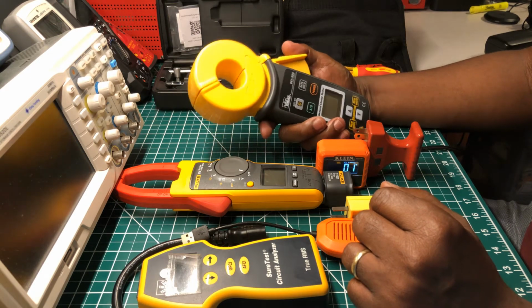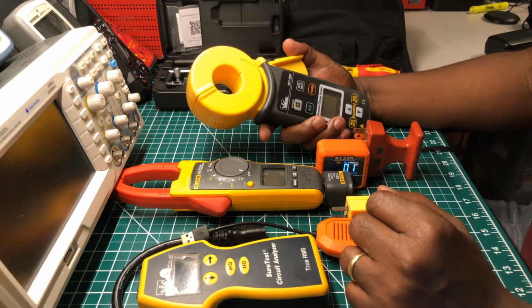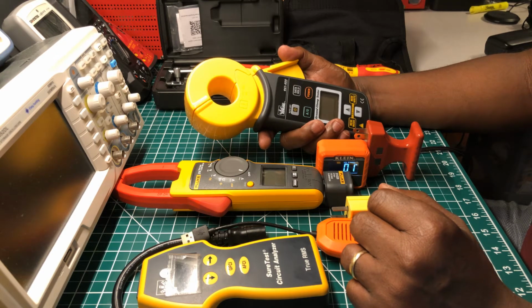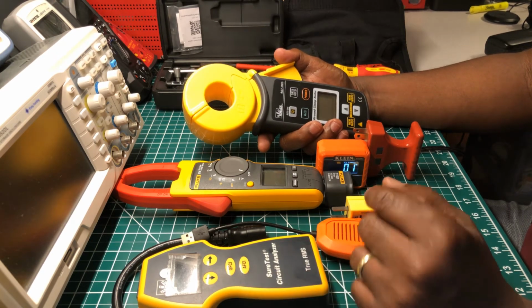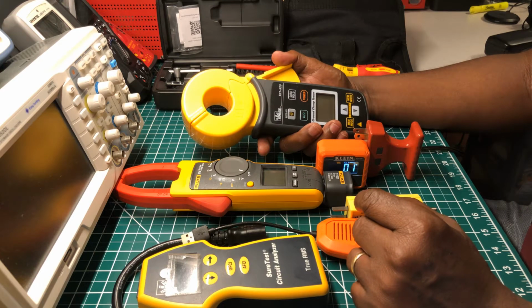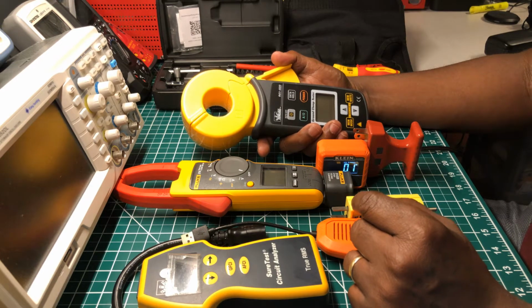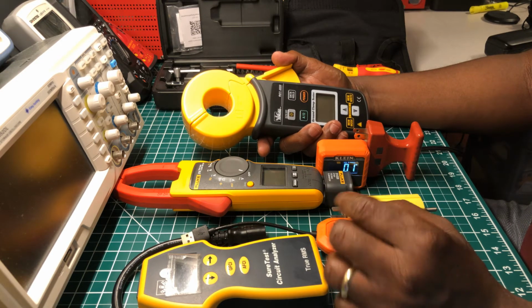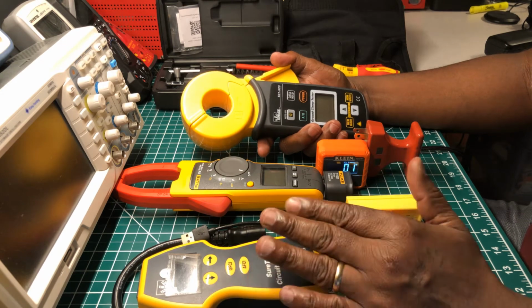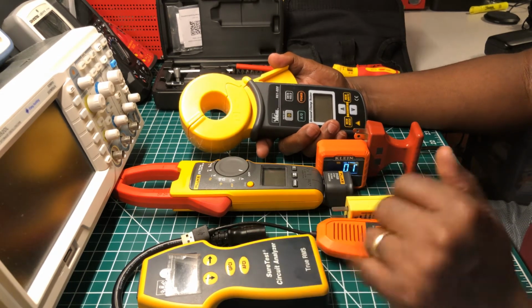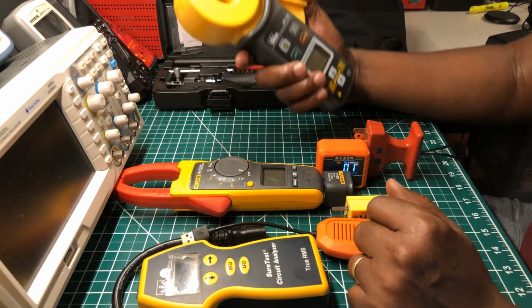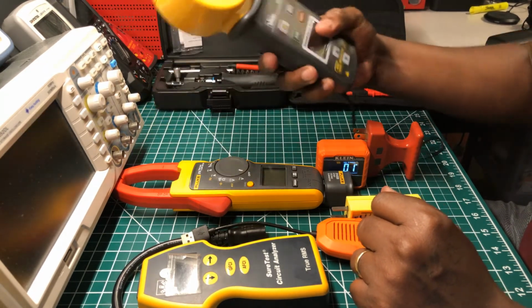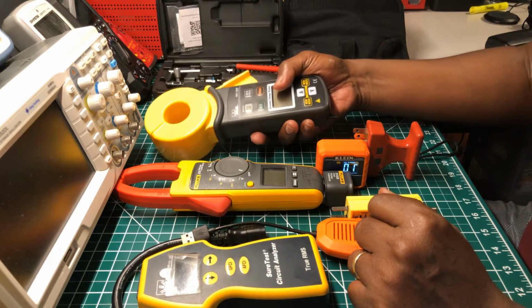So I go out and test my ground rod with this to make sure it's 26 and below for its resistance, and if not, I drive another ground rod to bring the resistance down. Oftentimes I like to put my ground rod where water often puddles up, and I'll put it right there. But anyway, this is what this is for, and this thing costs a pretty penny.